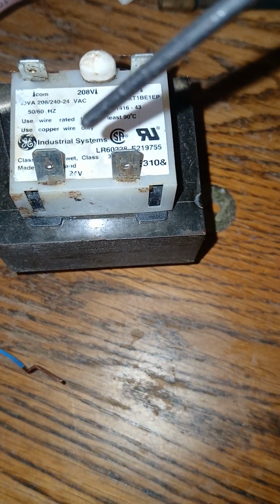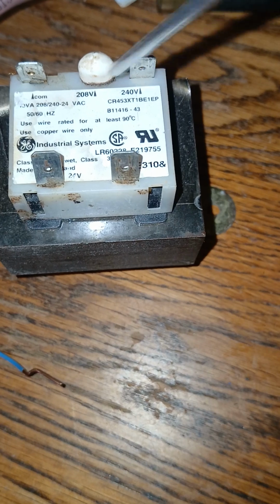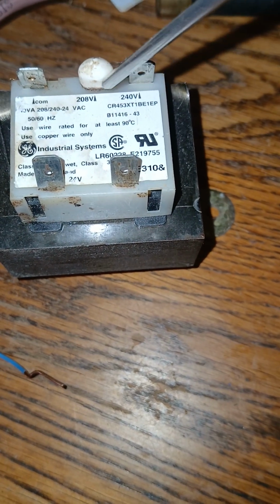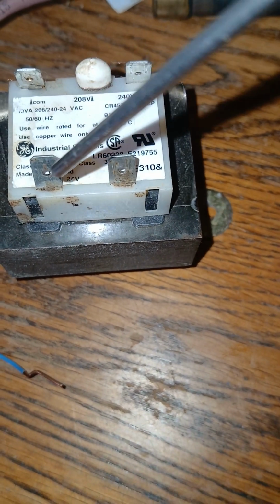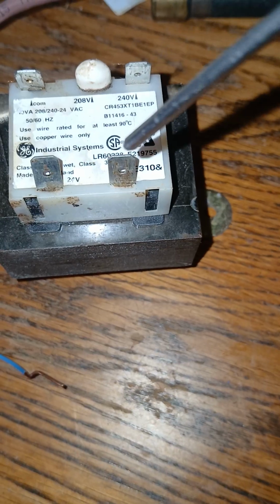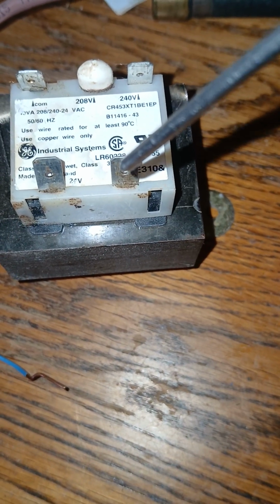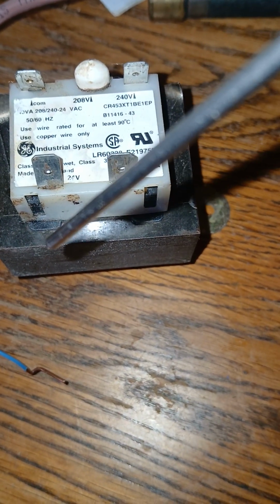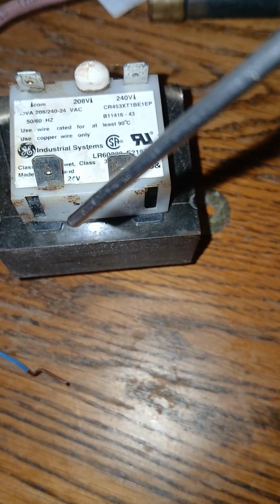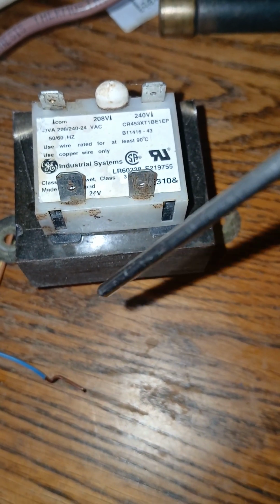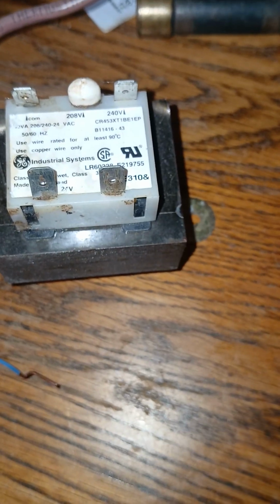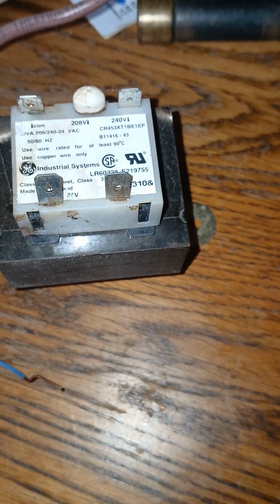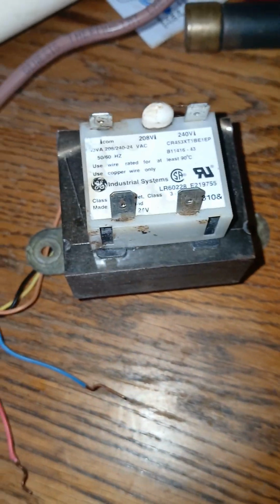So whatever the incoming voltage is, 240, 208, 230, whatever, but the outgoing voltage normally is 24 volts. So one leg would be hot, one leg would be common. So when the leg is hot and common, then this feeds, and then you start to go down and you feed the thermostat, the control board or whatever.